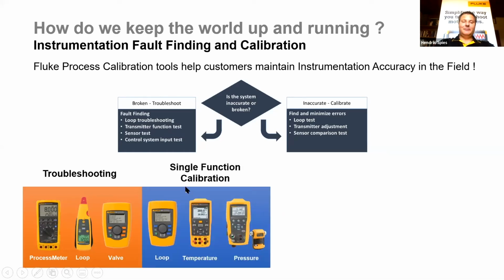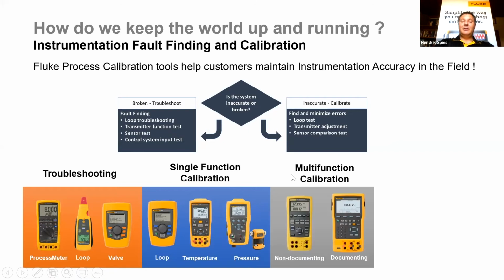Next is the single function calibration. We really want to do loop. So if you specifically look at loops, milliamp loops, then we have temperature for RTD or thermocouple and pressure. Depending on what pressure you want to work on, we have units with a built-in pump and with a hand pump. And if you go higher than 20 bar pressure, then typically we have modules available up to 690 bars. If you then look at the multifunction calibrators, we have non-documenting, which does RTD, thermocouple, your pressure, and then also the types of multifunction calibrations you want to do, like milliamp, voltage, and resistance. So there are quite a few parameters you can calibrate.